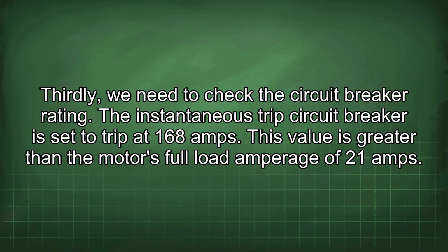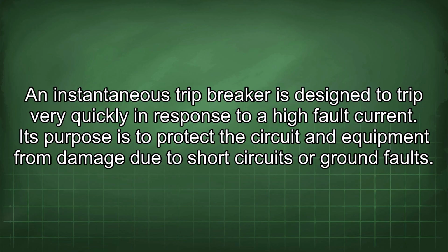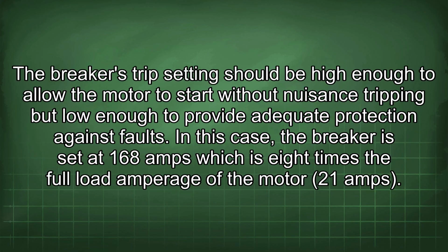Thirdly, we need to check the circuit breaker rating. The instantaneous trip circuit breaker is set to trip at 168 amps. This value is greater than the motor's full load amperage of 21 amps. An instantaneous trip breaker is designed to trip very quickly in response to a high fault current. Its purpose is to protect the circuit and equipment from damage due to short circuits or ground faults. The breaker's trip setting should be high enough to allow the motor to start without nuisance tripping, but low enough to provide adequate protection against faults.